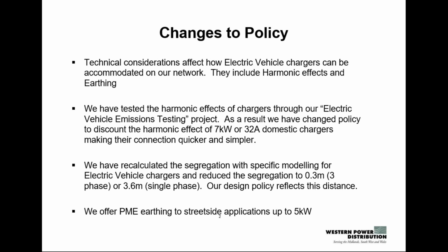The other thing we've done for streetlight charging is there's a whole world of regulation to do with earth zones and what can be connected to what. We've changed some of the standard UK calculations to reduce segregation, and another important thing is the PME earthing system, which is quite prevalent on our low voltage networks. We now allow for applications up to 5 kilowatts of streetlight charging.